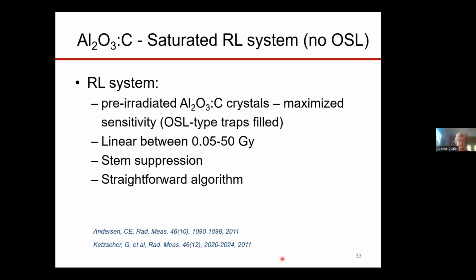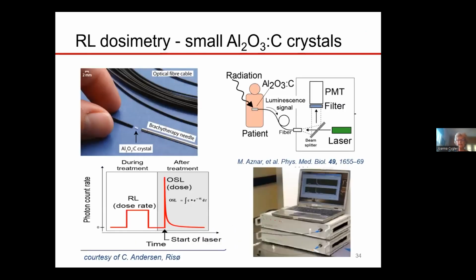That's a very nice system, and the whole idea was actually started in Denmark by Klaus Andersen's group. They did lots of work on that, and they developed a very nice system that actually has 2 modes of operation. One mode, based on radioluminescence, measures the dose rate, and the other mode, based on the OSL principle, measures the total dose after the treatment. The detectors are coupled to a fiber optic system, and it's all computerized and a really very elegant solution. I was lucky to actually use this detector in our clinic.